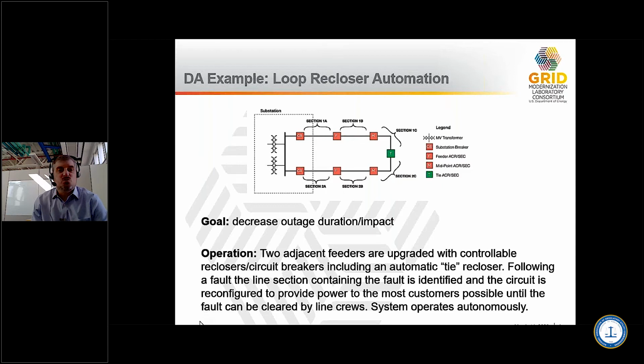But really the way loop recloser automation works is that you have a tie breaker, that's that green breaker there in the figure, and it is usually open, right? So basically at the point where two feeders meet, they operate normally radially, but that switch is usually open during normal operation. The idea is that if there is a fault, say a tree limb touches one of the overhead lines, for instance, within one of the sections, say section 2A there at the lower left, the system automatically detects that fault, clears that fault, right? Actually responds to that fault by opening, say, a circuit breaker.